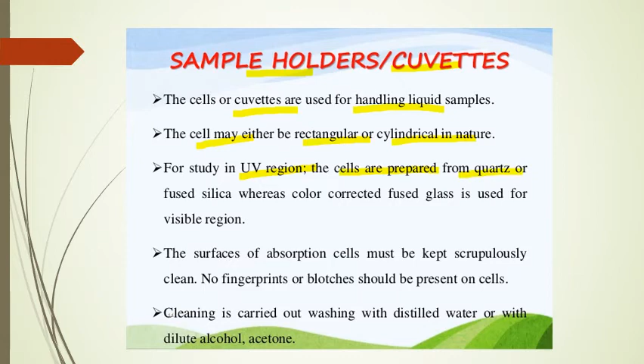The sample holder is the third feature in UV visible spectroscopy. Always a cell or cuvette is used for handling liquid samples, and for UV visible spectroscopy a transparent solution should be used, as you have seen in the absorption law. If your sample is solid, it should be dissolved in a solvent, and that solvent is taken as a reference. The cell may be either rectangular or cylindrical. For study in the UV region, the cells are prepared from quartz or fused silica, whereas color corrected fused glass is also used for the visible region.